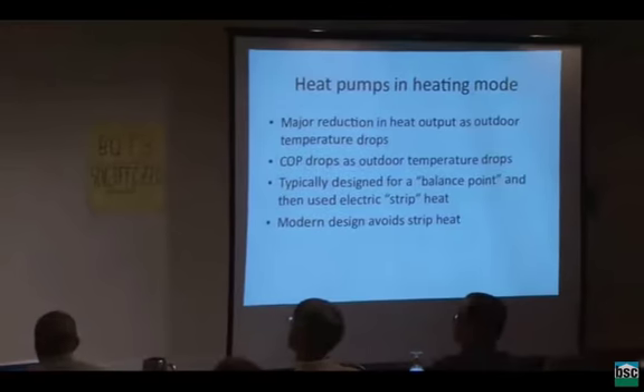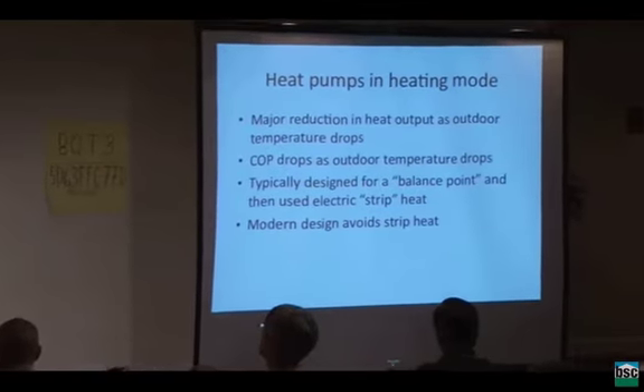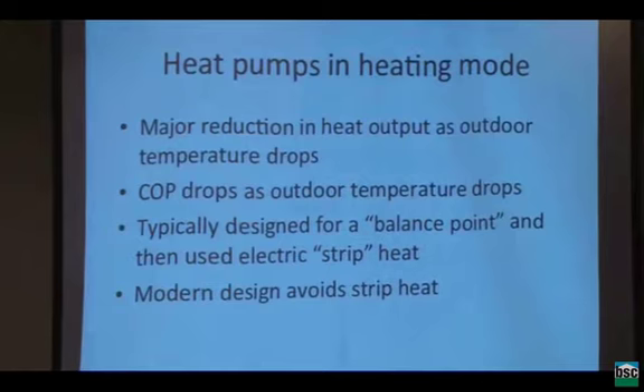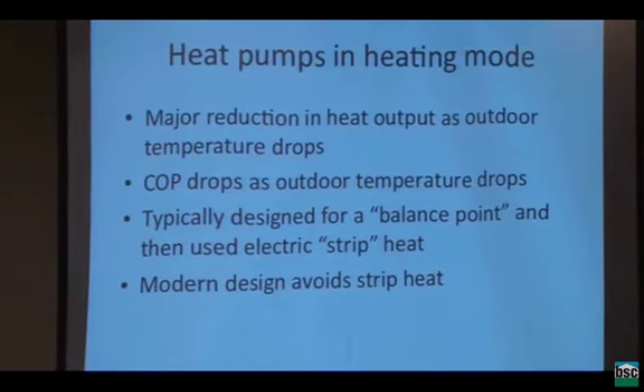So in heating mode, the challenge is that the lift is much larger. In air conditioning mode, the return air temperature might be 75. The outdoor temperature might be 95 or 100, maybe 105 at extreme. That's only 25 or 30 degrees. In heating mode, the return temperature might be 70 degrees, but the outdoor temperature could be 0. That's a 70-degree lift. So it's at least twice as hard to get heat from 0 degree outdoors as it is to reject heat to an outdoors at 105. And that makes the equipment slightly different, and it makes it less efficient in heating mode.